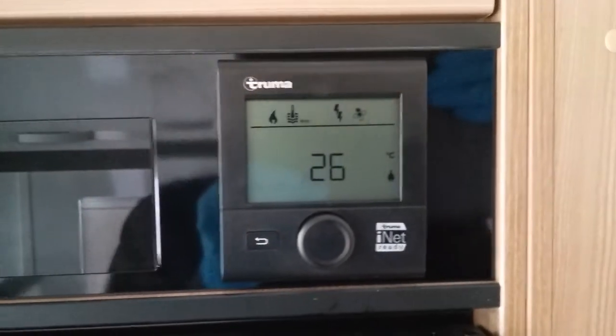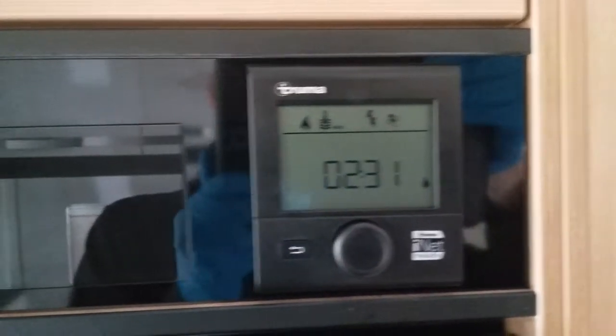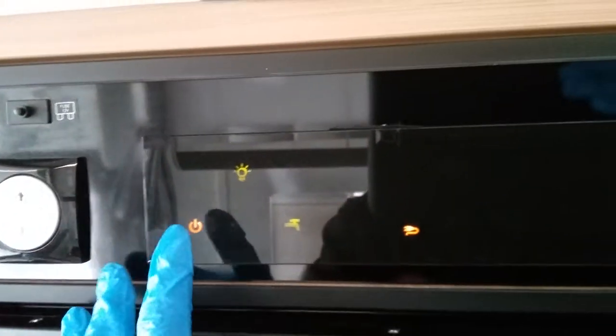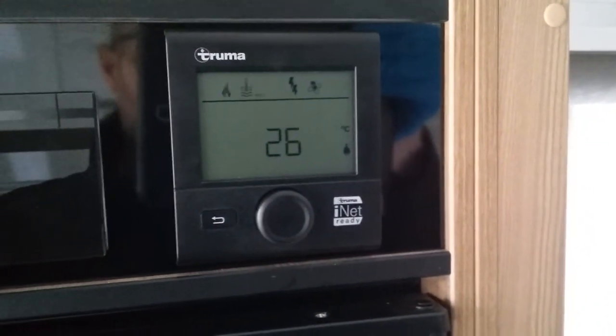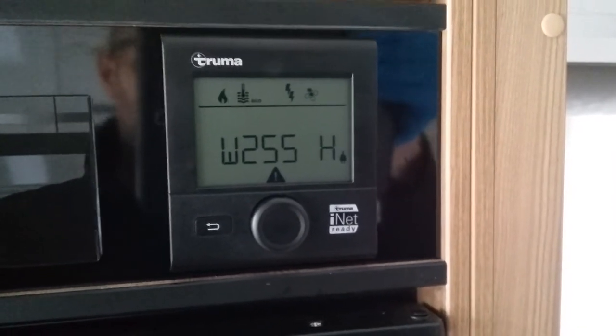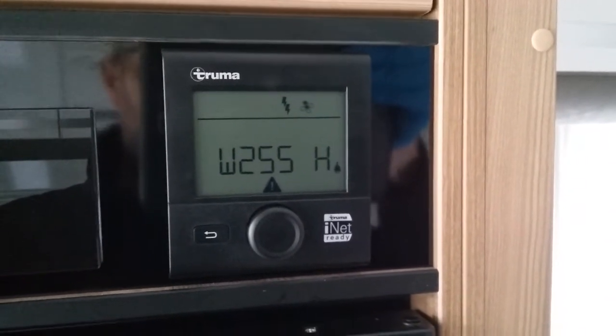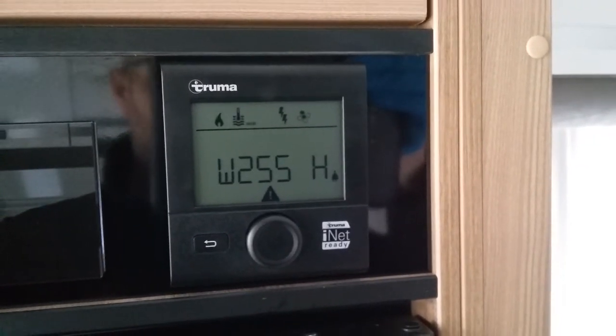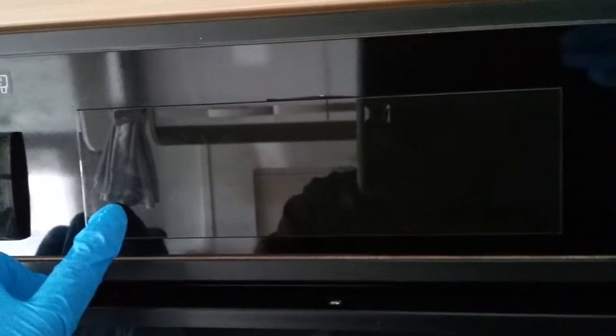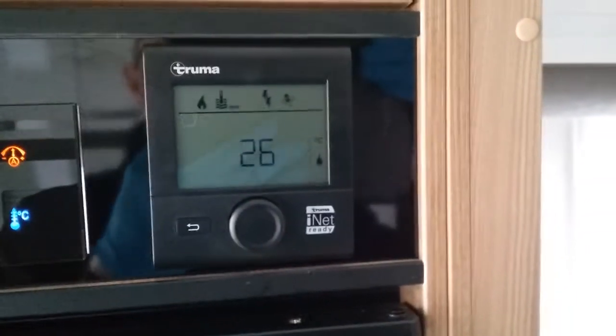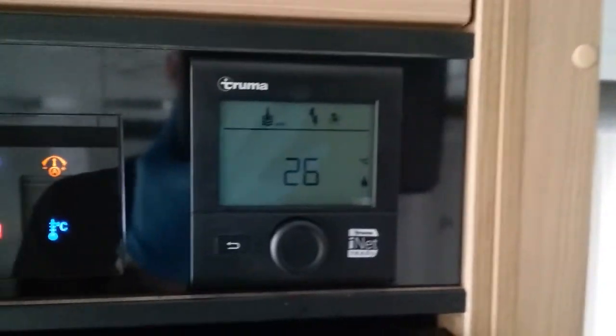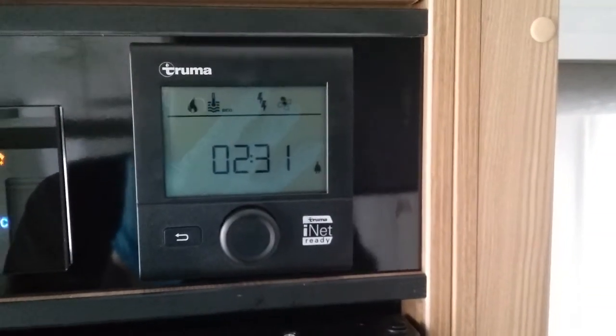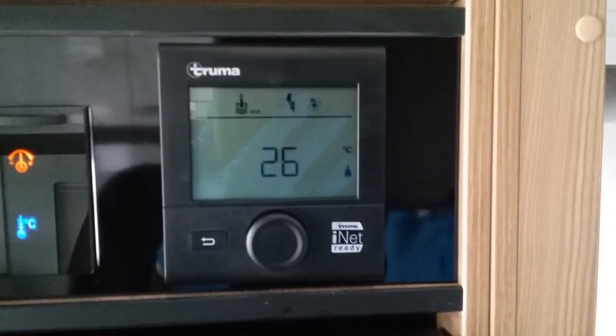I can actually make this throw up an error code now by turning off the main control panel. If we hold this down until it says off and then return, in a moment we should get an error code appear. W255H is the error code for losing 12 volt, because we've turned the 12 volt off. If I now turn the control panel back on again, the error code should automatically disappear because we've rectified the problem. Nine times out of ten it will just disappear once you sort it out.